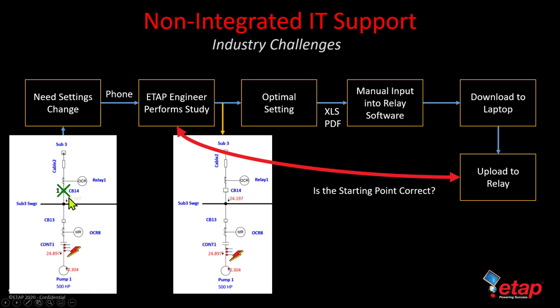Here we can see that relay 1 operates first versus OCR 8. So therefore there's a need to change the setting and optimize this condition, and that might be triggered through a phone call or an email to an ETAP engineer who performs the study. They essentially go into a revision and they perform a coordination study where they improve the optimization of the protection settings, and they generate an optimal setting. Now, if you recall, the setting file is different from a setting report. So the optimal settings are then emailed through Excel or PDF to another individual who would essentially convert that manually into the relay software and generate a setting file, which is then downloaded to the laptop and then finally uploaded to the relay. A question to also ask here is that when the engineer performed the study, did he use the correct starting point to do this assessment and evaluation in the first place? So there's a lot of unknowns through this non-integrated business process or workflow.